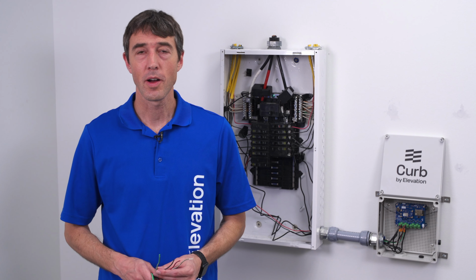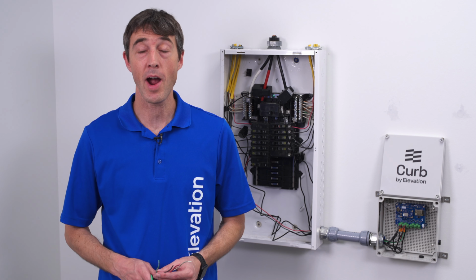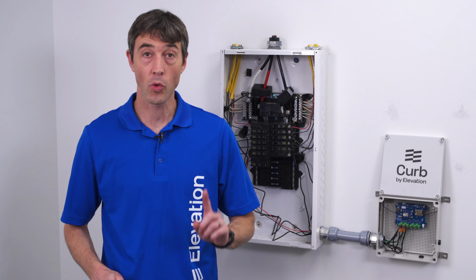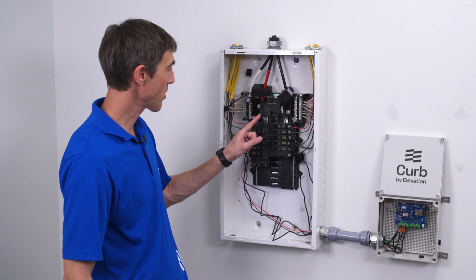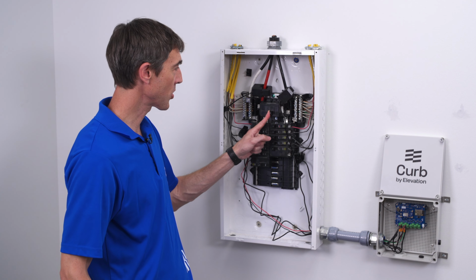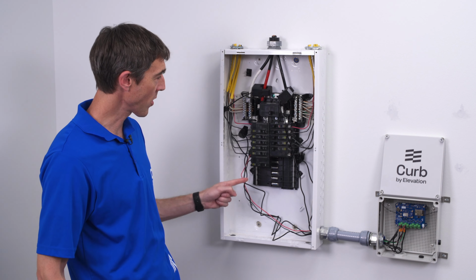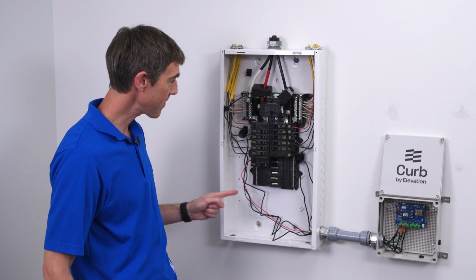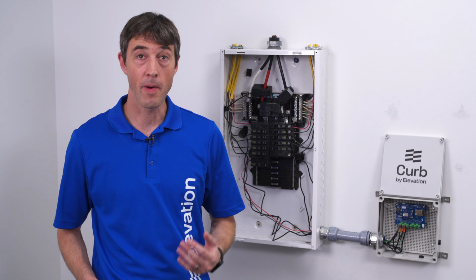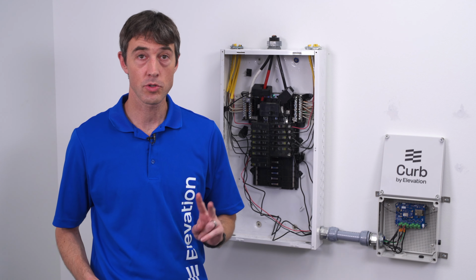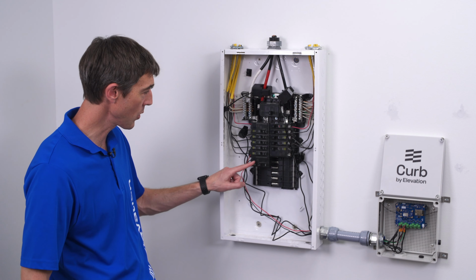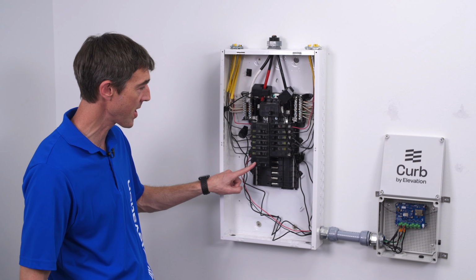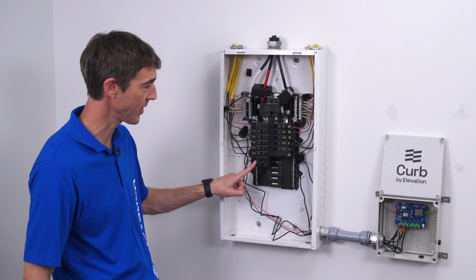Step 2 of installing the Curb device is getting power to the Curb device. Before you start this one, make sure that you turn off the main power from the electrical panel so that there's no power flowing into the system. The Curb is powered by a new 20 amp 2-pole breaker. As you can see, we've installed a new 20 amp breaker right here that powers the Curb device.